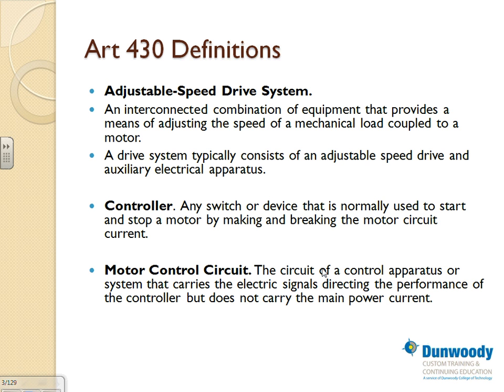It can control speed. You can run the equipment at multiple speeds. Who cares? I always say, who cares? You can control the temperature in this room, right? With an air handling unit, by controlling the speed of the air handling unit blowers, you can control the temperature in this room. So here's what they define: an interconnected combination of equipment that provides a means of adjusting the speed of mechanical loads coupled to the motor.